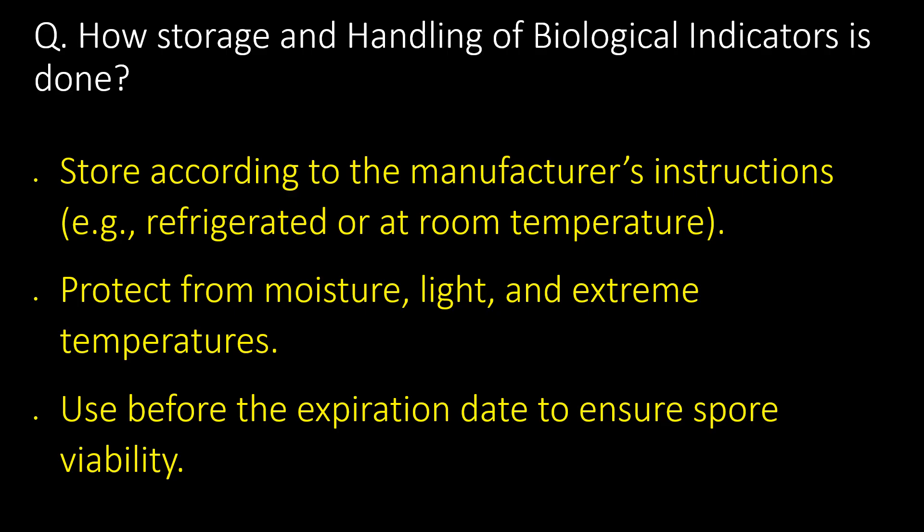How is storage and handling of biological indicators done? Biological indicators are stored according to the manufacturer's instructions, for example at refrigerated or room temperature. They should be protected from moisture, light, and extreme temperatures. Biological indicators shall be used before the expiration date to ensure spore viability.